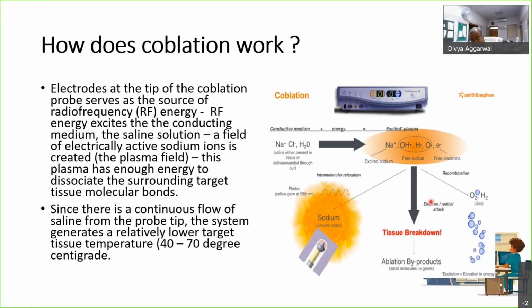So this is a very complicated diagram. You would get confused, but still I have put this diagram. Electrodes at the tip of the coblation probe serve as the source of the radio frequency energy. As I said, even coblation works with radio frequency energy. Now, what radio frequency does is that the radio frequency energy excites the conducting medium, which is the saline solution. A field of electrically active sodium ions is created. This plasma has enough energy to dissociate the surrounding target tissue molecular bonds.